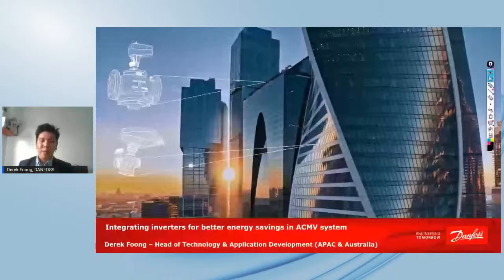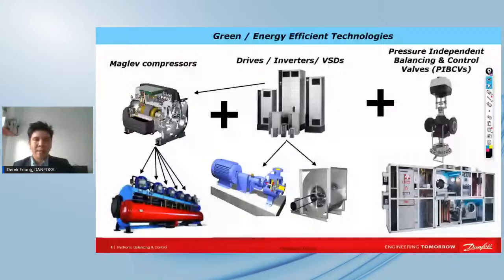So now, a little bit in the beginning, when we talk about efficient technologies, these are the key components that we regard as key technologies. On the left-hand side, we have magnetic levitation compressors. In fact, it is a centrifugal compressor which is oil-free, and it is powered by a small voltage to lift the compressor and rotate without friction. It is fully vacuum, and it can rotate up to thousands of rpm with an inverter. This has been one of the most demanded components this decade, and we have more than 80% market share for this. The trend is also working this way.